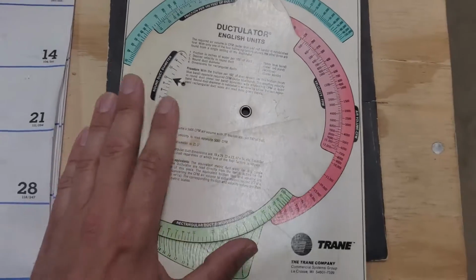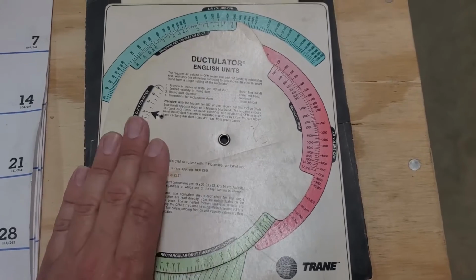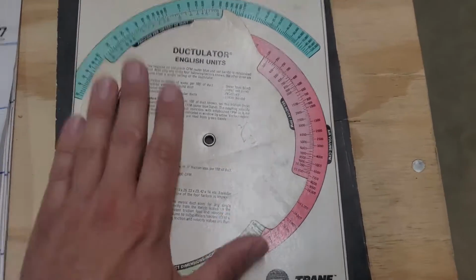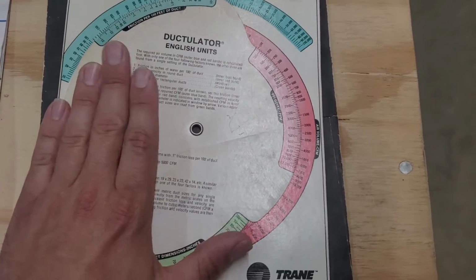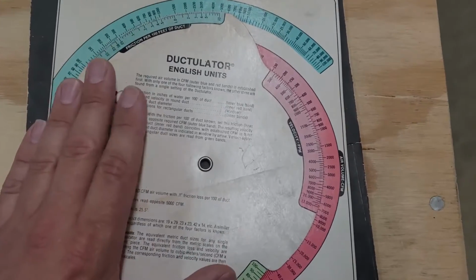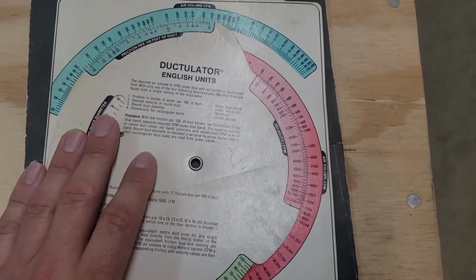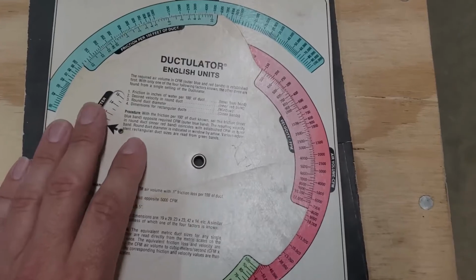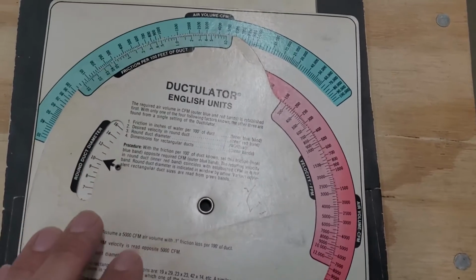So that's number four, wire size. Number five, ductwork, how do you calculate ductwork? You've got to learn how to calculate ductwork. Get a ductulator and figure that out, because in the field a lot of problems are just airflow. This is a ductulator, and I prefer this over any phone app just because it's a very good hands-on way for you to figure out in the field if your duct is sized properly, if you're designing duct. Most sheet metal professionals use ductulators.